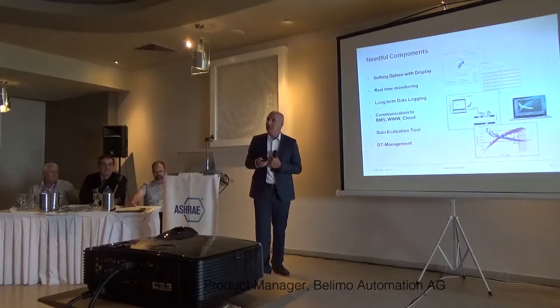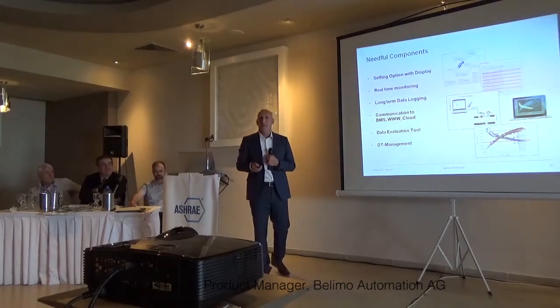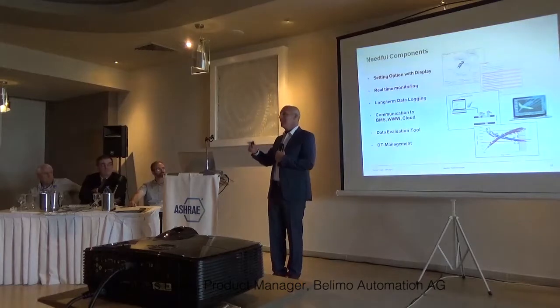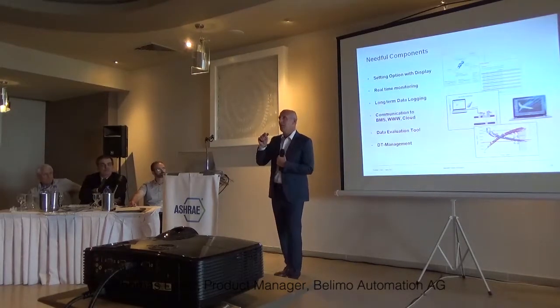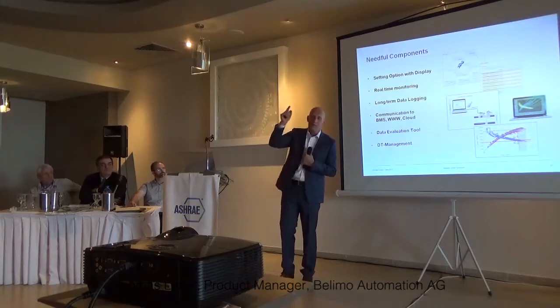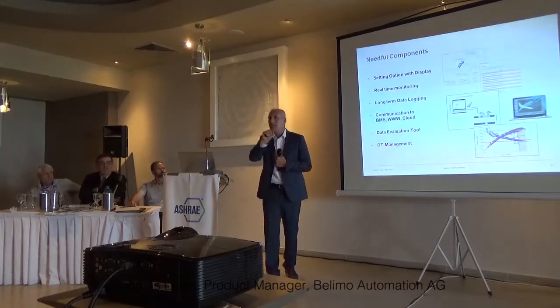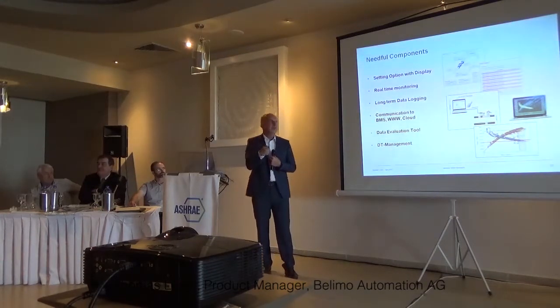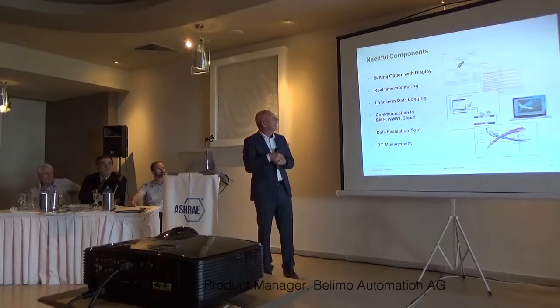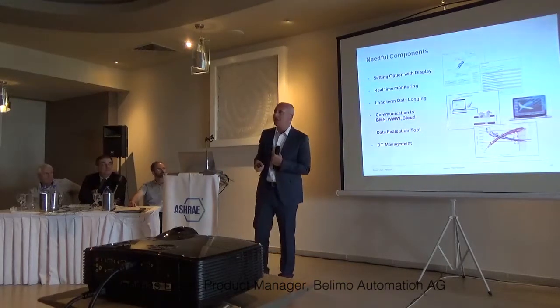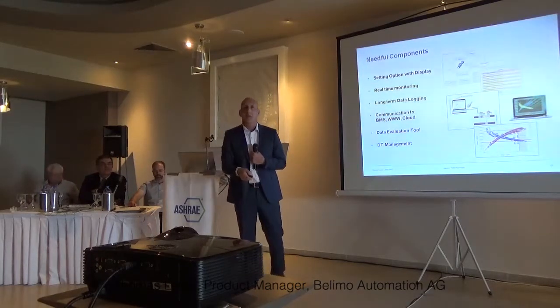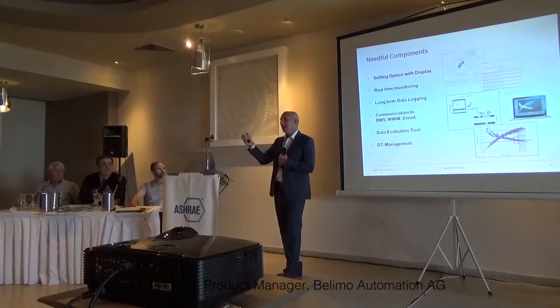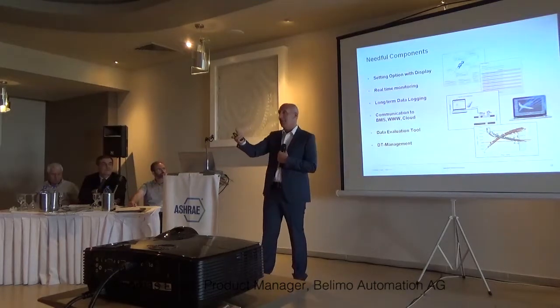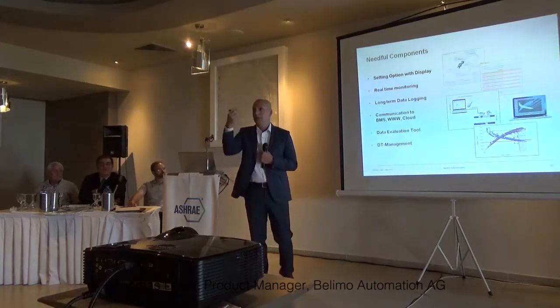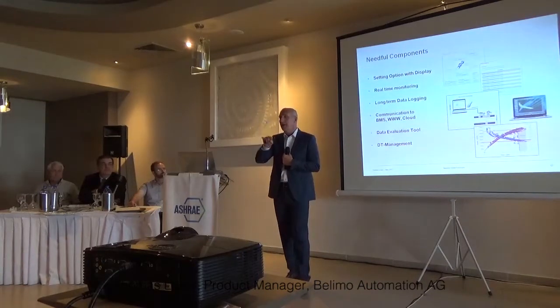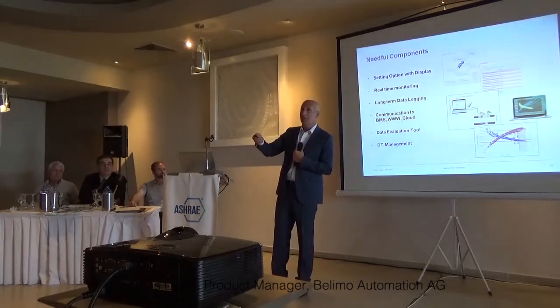Monitoring is a big issue. Transparency, what I mentioned before. To have the chance to watch what is going on. Where is a huge consumption? Where is the delta T in my building? Inside this spot. Want to know all this, also very important. Data logging. Data logging to do the preventive maintenance schedule. A good value is if you have it more than 1 year, let's say 13 months, every 20 minutes, so that you can really see over the year what was going on.